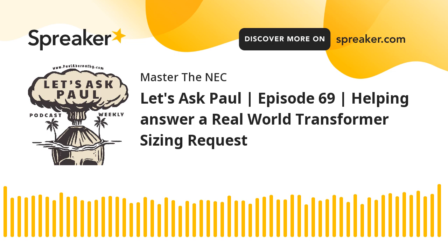So that's going to meet item number 2, which tells me, since I had to have 100 amp for the HVAC, that it has to limit the load onto those secondary conductors, and it can't be less than the device that's going to limit that load. Since it's rated 100 amps, my conductor is not going to work because I can't use that next size up rule for my conductors. So I'm going to have to jump from the 4 up to the 3, which is good for 100 amps. I'm going to run 3 gauge from the secondary up to the disconnect, and then from the disconnect down to the HVAC, I can drop back down to 4.